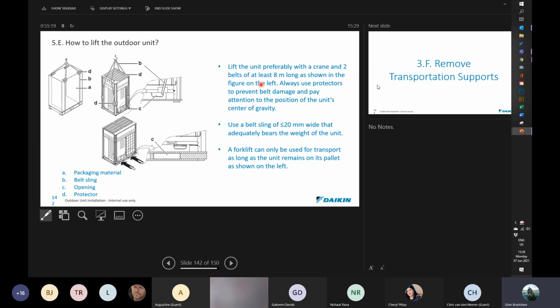All right, so yeah, quite a lift. If I think back to my days in the industry with lifting things, it was often that day that was actually quite stressful because quite a bit of planning had to go into it. So in terms of that as well, often when we arrive on site, we see damage to units, and it becomes pretty obvious that it was because the lifting was never done properly. Slings are too tight, they start pulling the top of the unit in, and then we see the telltale marks of sling damage and things like that. So take note of the lifting requirements.